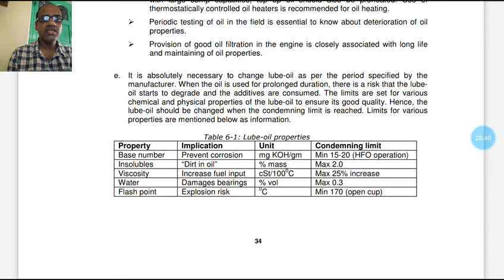Insolubles, that is dirt in oil, indicating contamination. Unit in percentage of mass, maximum 2%. Viscosity, which increases with fuel input, measured in centistokes at 100 degrees centigrade. Maximum 25% increase. Water damages bearings, percentage volume, maximum 0.3. Flash point, explosion risk, in degrees centigrade, minimum 170 degrees for open cup.